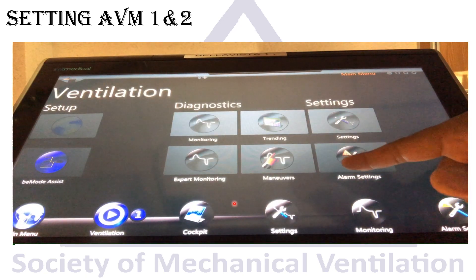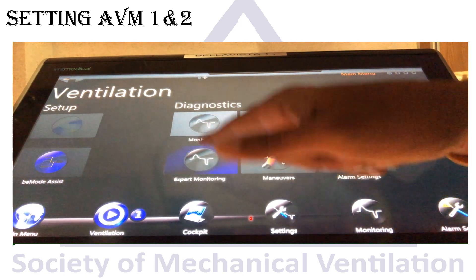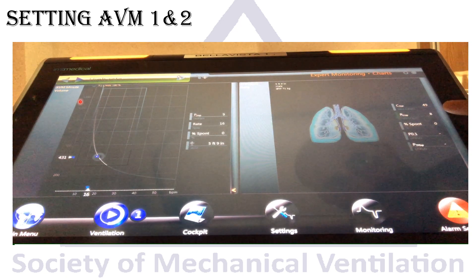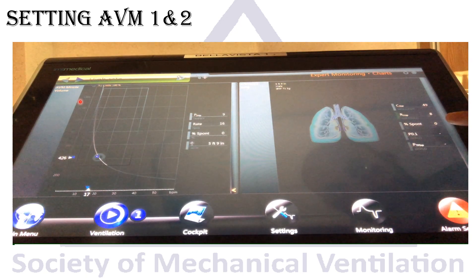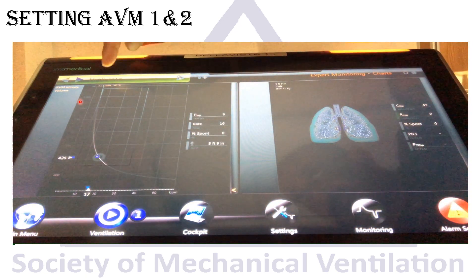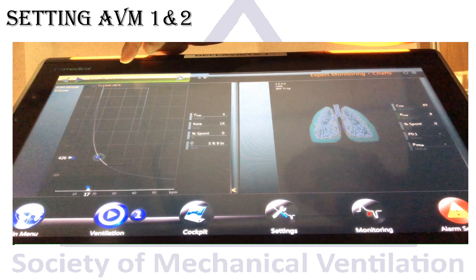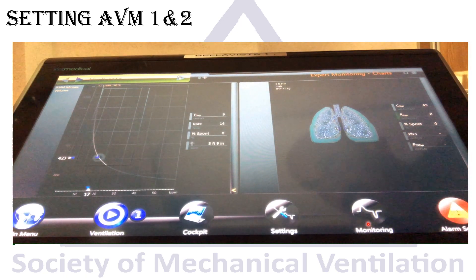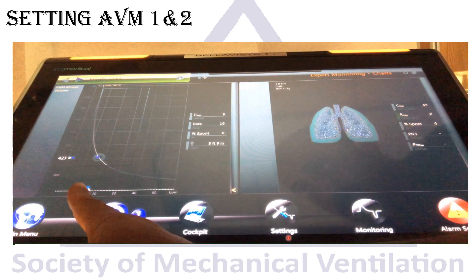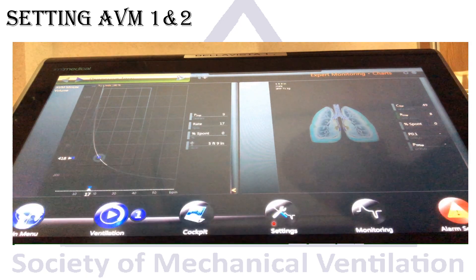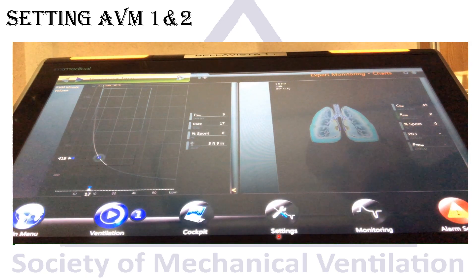Now let's go to the expert monitoring screen to see the curves. This is the animated lung, which gives you compliance — here we set compliance to 50 and resistance to about 10, and the ventilator is measuring resistance at 8. There's no spontaneous breathing here. This is the AVM minute volume window: you'll notice the target is 7.1 liters at 100%. Based on the equation we described, the ventilator targets approximately rate 17 and tidal volume of about 418 mL.